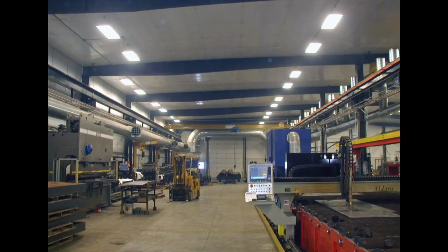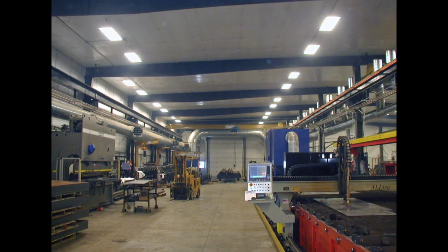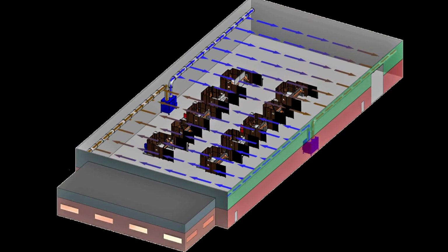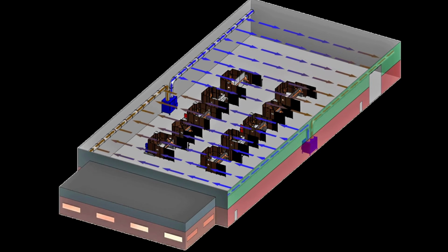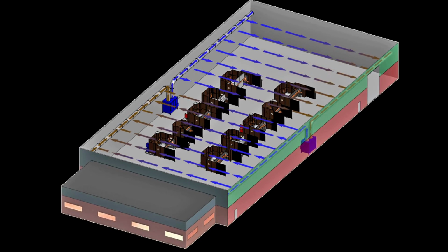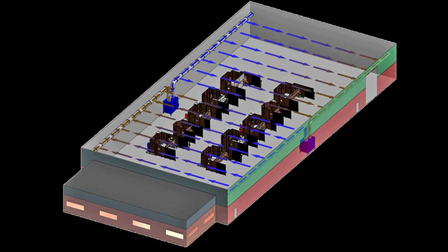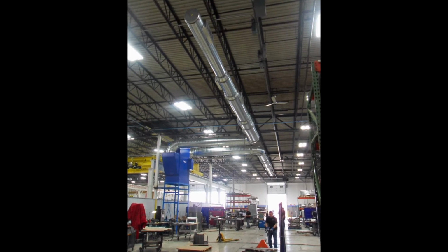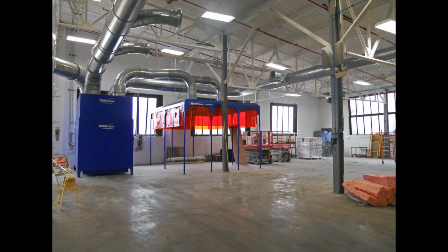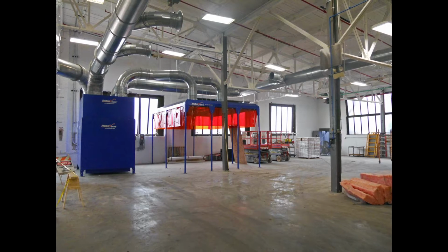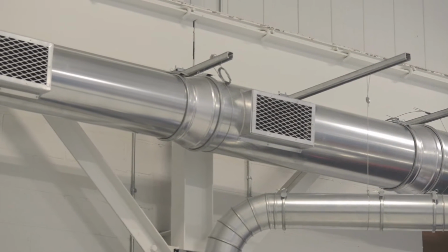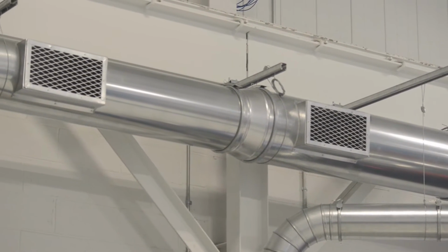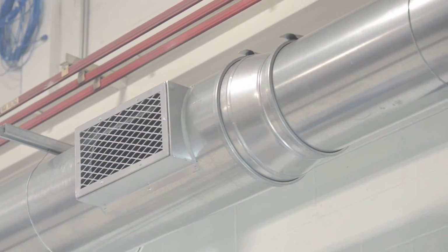of success. Recently, a commonly applied system is the push-pull method, where the air is blown out from one duct run across the factory and drawn to the intake duct on the opposing side, simultaneously capturing the airborne particulate. Push-pull has proved to be effective at removing the airborne pollutants from the factory air, but there are inherent limitations and restrictions in applying this method.